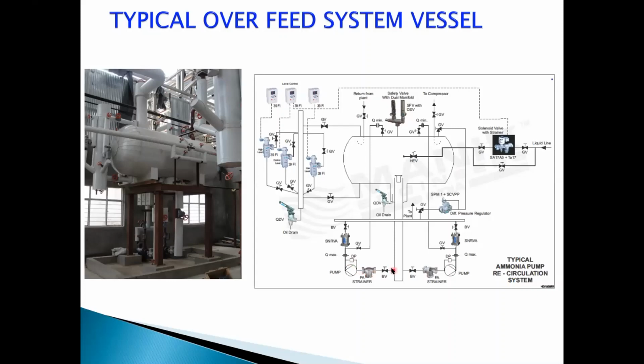When we have bigger systems, we have multiple pumps, maybe one working and one standby. So we put a non-return valve in the pump outlet. So if one pump is working and another one is not working, then the pressure will not come on to the non-working pump. So this is a typical pump vessel installed in the plant. This one is for -35. You can see the level controllers, solenoid valves, the ammonia pumps.